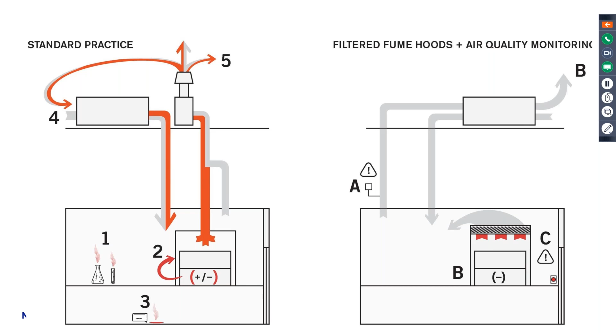Big piece of how we get to net zero, we replaced all the ducted fume hoods with filtered fume hoods, significantly reducing the size of all of our air handling equipment, including 100% outside air handling units, our exhaust air system, and all associated ductwork. An air quality monitoring system, Aircuity, continuously monitors room VOC levels, increasing and decreasing ventilation and exhaust air as needed.